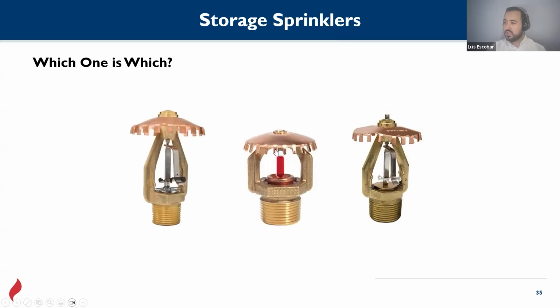What can we say about these three sprinklers? We saw that there are different orientations for them. For example, we had pendant, we had upright, and also we had sidewalls. These three are upright heads, because they're oriented upwards. The activation method for these two on the edges is the fusible element, and for this one it will be a bulb. When this one breaks, the water starts releasing. And there are a lot of finishes for them. They can be corrosion resistant, they can be brass, chrome, and I mean there's a very vast category to choose from.